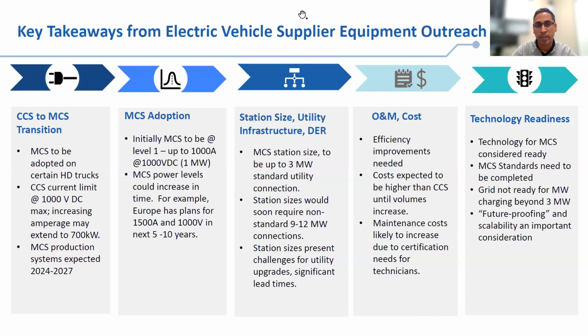Then we have the utility side of this, where we have station sizing. Today 3 megawatts is basically the standard utility connection, give or take, 2.5 to 3 megawatts. We anticipate station sizes to go to 9 to 12 megawatts in the near term, and up to 25, as Salim pointed out. This is going to cause significant utility upgrades with significant lead times, as most of you are already experiencing.